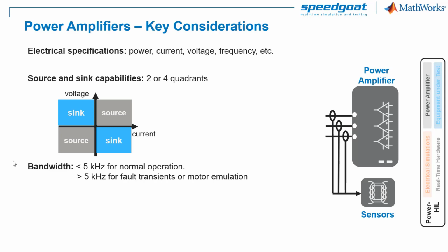Bandwidth is key. For simple AC grid emulations, bandwidths of 1 to 5 kHz may be enough, but bandwidths of 5 kHz or higher are preferred for harmonic, fault transients, transformer saturation, and motor emulation. An important feature is for power amplifiers to track either voltage or current setpoints. This will be relevant when choosing your interface algorithm. Voltage tracking is typically used for grid emulation, while current tracking can be used for emulating a load, such as a motor.